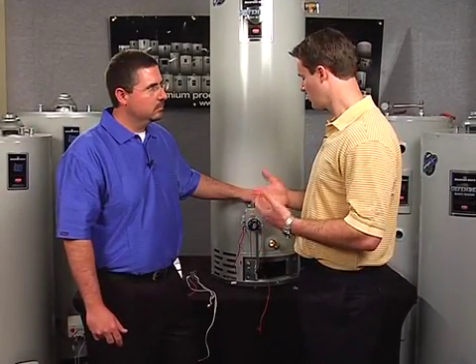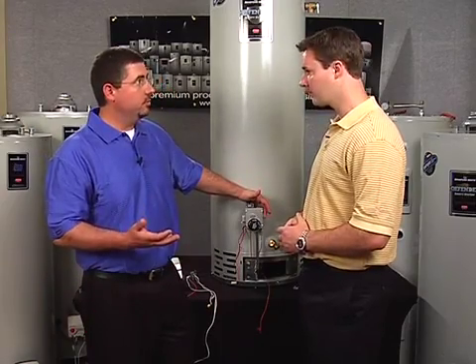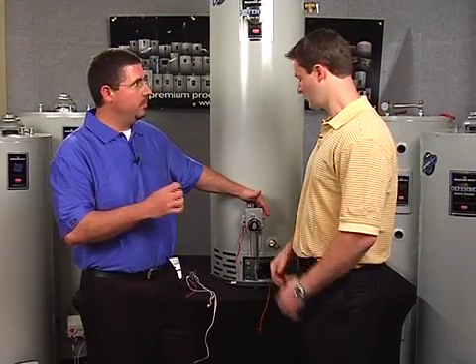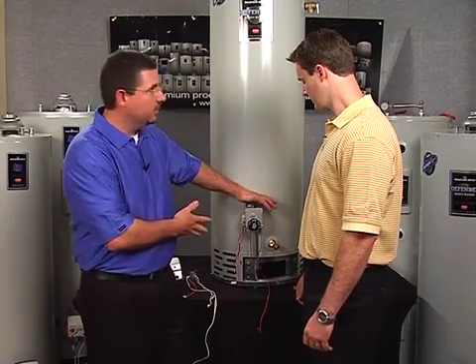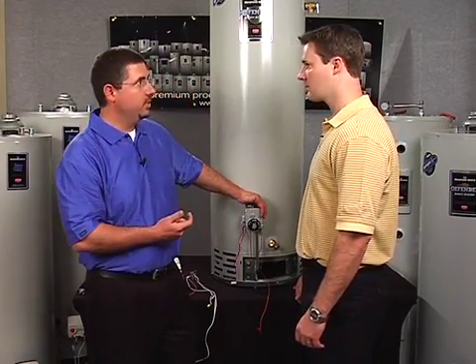Can the ICON system be used to replace any older control — either a White Rogers or a Robert Shaw, pre-FVIR or FVIR water heater? Yes, it's set up as a universal control, so it will be able to replace both Robert Shaw and White Rogers, Flammable Vapor and before. Remove the outer door and inner door, and we'll go through the changing process.